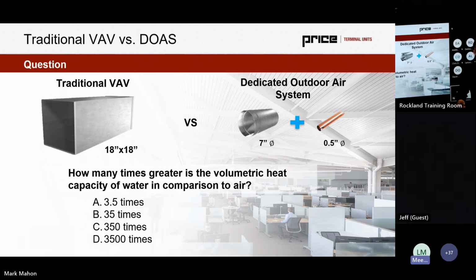D is the answer. The rationale here is we have about 1,000 to 1 density from water to air, and then the coefficient of heat performance for water to air is about 3.5 to 1. So we multiply those together, and we get the volumetric heat capacity of water in comparison to air, a very impressive number that you can walk into your narrative meetings with owners and say, this is why you use DOAS. But the point here is, it's a lot easier to move energy through water than it is through air. Any questions on that?